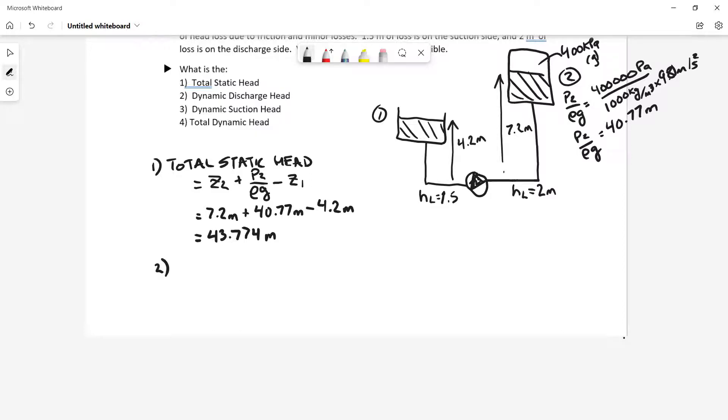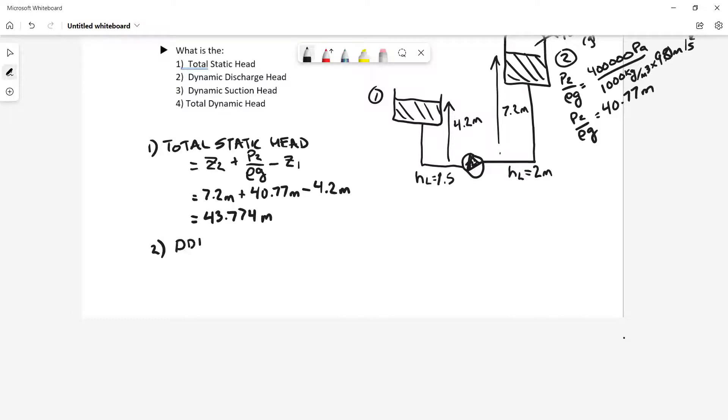Okay, so I also have my dynamic discharge head. And as we worked out before, my dynamic discharge head is going to be equal to my dynamic or my static discharge head plus my discharge pressure head plus my head loss on the discharge side minus my velocity squared over 2G leaving the pump. Okay, so the velocity in this case is zero. And what I'm left with is my head height 7.2 meters plus my pressure head 40.77 meters plus 2 meters of head loss.